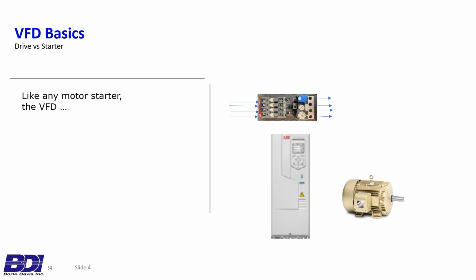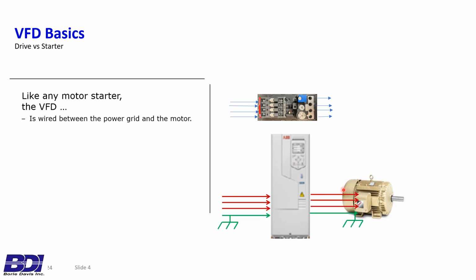So just some starter versus VFD comparison. Here's a simple starter, and it's just a contactor with a set of thermals on the connected together. Well, the drive has thermal overload protection, and the drive sits between the power supply and the motor, just like a starter does. The drive starts and stops the motor, just like a starter does, but the drive starts at 0 voltage, 0 frequency, whereas a starter says 460 volts, 60 hertz, all ahead full right now. So that's that inrush concern. Each has motor overload protection, because you've got to protect your motor from an overload condition. We'll get to the seriousness of that in a minute.